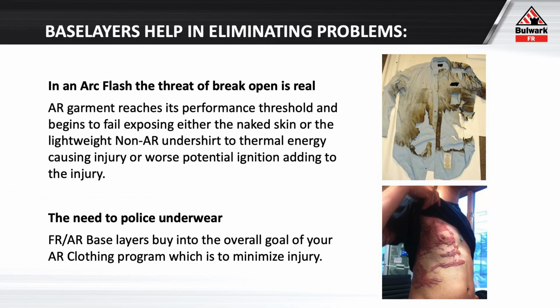If this has a break open, an EBT, then I know where it's going to break open at. What's my point? If I introduce more incident energy than this can insulate and protect against, it's going to fail. The picture of that shirt you see there worked perfectly, but there's just too much incident energy for the arc rating of that garment, and you're starting to see failure.